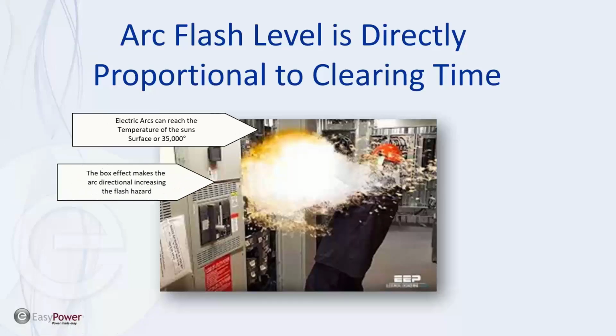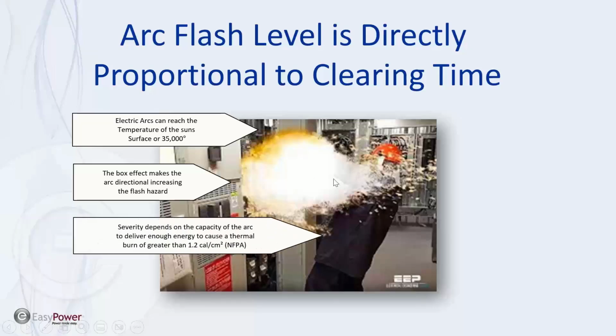So it's 35,000 degrees. In a box, it's going to be a little worse, about 10 times greater than it would be in open air, because of the directional type of system. Like a cannon, it's going to go in one direction. And so we talked about the severity depending on what the level is, and it's not an arc flash class, so I'm not going to get into the calories and so forth.